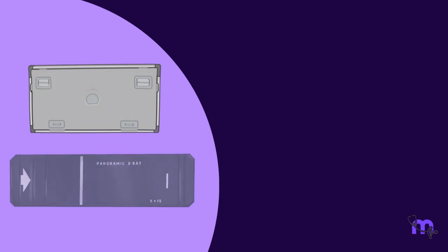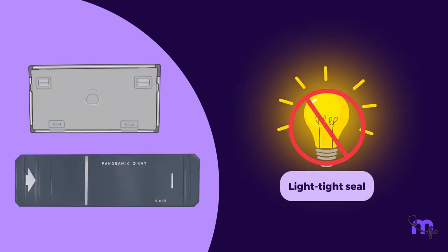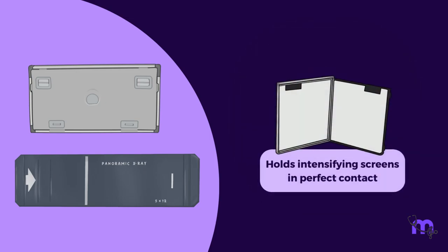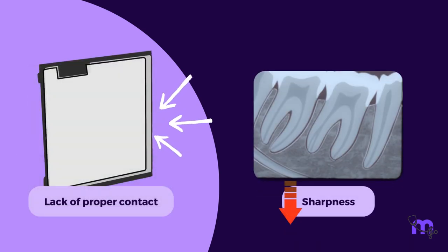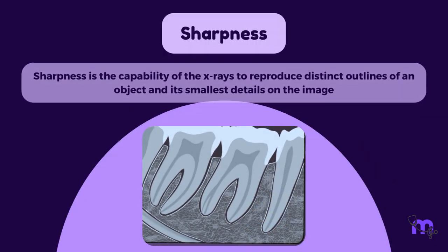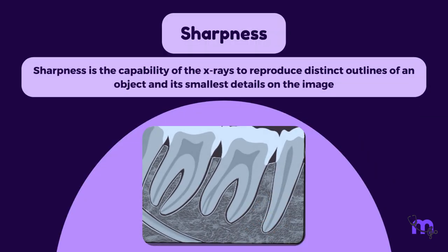Both rigid and flexible cassettes have to be light-tight to protect the extraoral film from exposure and to hold the intensifying screens in perfect contact with the film. A lack of proper contact results in reduced image sharpness. Sharpness is the capability of the X-rays to reproduce distinct outlines of an object and its smallest details on the image.